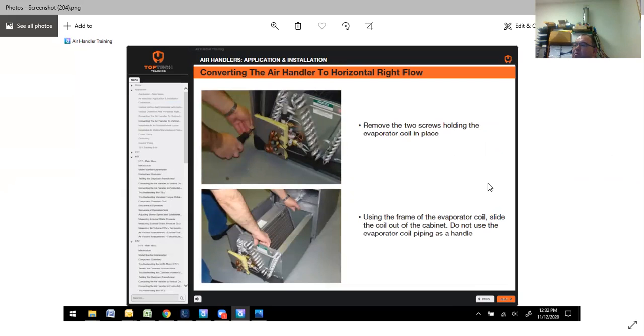Remove the 2 screws holding the evaporator coil in place. At that point, you can use the frame of the evaporator, slide the coil out of the cabinet. It does tell you do not use the evaporator coil as a handle. It's aluminum, even if it's copper. If you try to start yanking on that, you could and may very well break that. So use the actual frame itself.